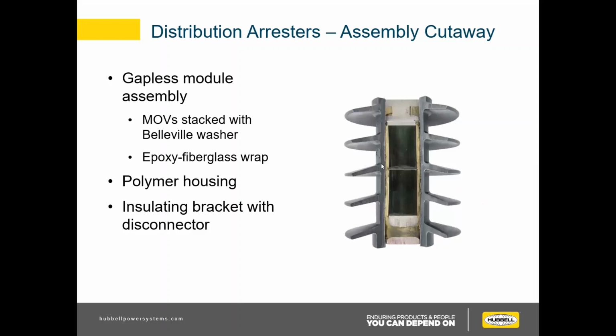So here's a little more detailed cutaway. The green here is our MOV blocks. In the picture before, you can see that the MOV blocks are white. They're actually covered in a glass coating, which helps with moisture ingress and a little bit of durability for the assembly process. And then you can see our aluminum terminals here and our wrap pattern here.